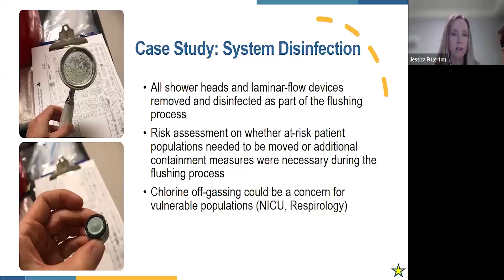Kathy already mentioned the issue with dead legs. Legionella loves that optimal growth temperature between 25 and 45 degrees, and it loves slow-moving, stagnant water, so dead legs certainly contribute to that. In very large, older healthcare facilities that have been renovated over the years, we end up inheriting a lot of these dead legs, unfortunately.